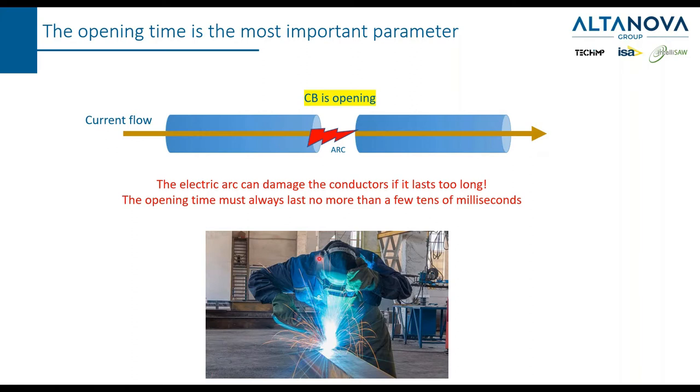The arc must remain for the least possible time. That's why it is extremely important, and we can say that the most important parameter that must be verified during the testing of a circuit breaker is the opening time. The arc is going to damage the surface of the two conductors, and when I say fast, I mean that everything must happen in a few tens of milliseconds.